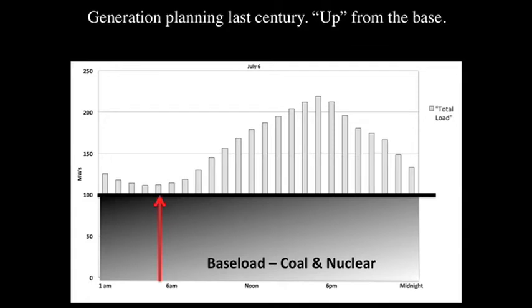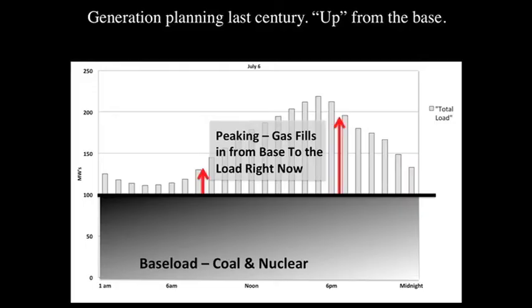The way to think about a base load power plant is like an aircraft carrier. It's a gigantic machine — it's not made to slow down. If you slow it down, it gets less efficient and burns more coal for every kilowatt hour produced, and it gets dirtier, making more pollution per kilowatt hour. Additionally, that great big cost isn't spread out the way it needs to be. To meet the load, you need something nimble and quick — that's what natural gas peaking power plants are for.